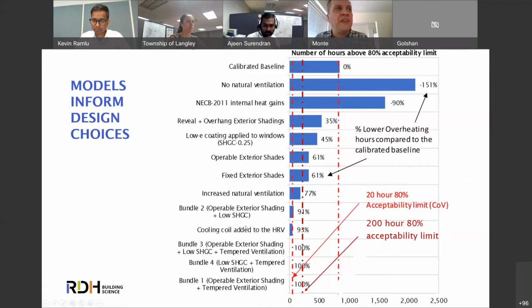Some of these bundles did get you there. Operable exterior shading plus low solar heat gain coefficient glass, which is what we originally specified, would have kept the building cool. Adding a cooling coil to the HRV would have kept the building cool. Doing both would have dropped you to complete cool. So there was no reason to add air conditioning to this building, ever.